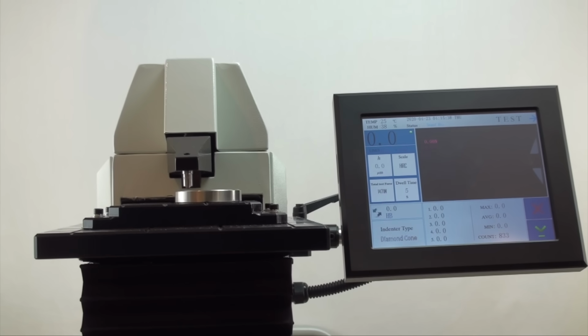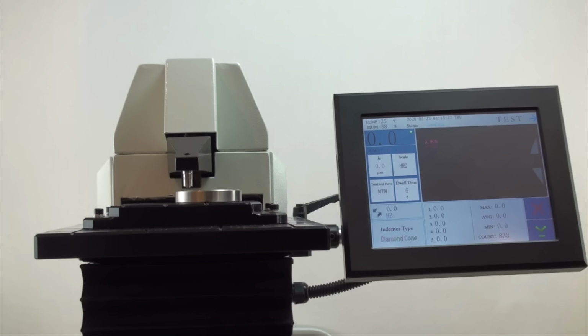Taking a test is as simple as affixing your test block on the anvil and pressing the start button. The tester will handle the rest of the testing procedure on its own. The motorized Z-axis will perform a test at any height position. However, it is better to be near in order to cut delays in testing time if that is of importance. The hardness reading is showing on the left and also on the statistics screen on the bottom.